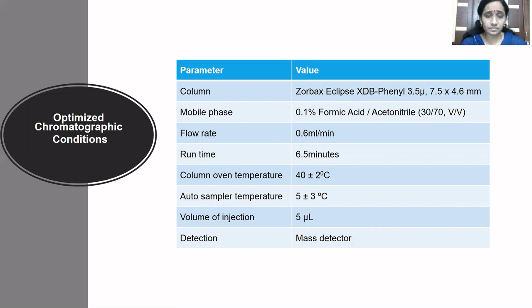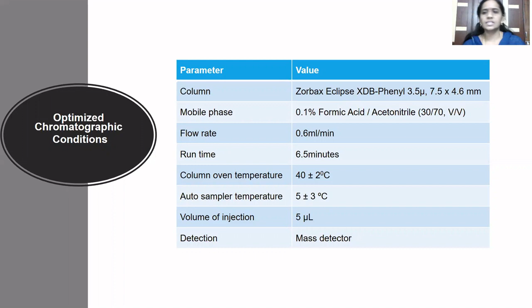Here, these are some parameters and their values mentioned in the paragraph is column. The Zorbax Eclipse XDB phenyl column is used, having 3.5 micron, 7.5 by 4.6 mm, and the mobile phase is formic acid and acetonitrile in the ratio of 30:70 volume by volume. The flow rate is 0.6 ml per minute, the runtime is 6.5 minutes, autosampler temperature is 5 plus or minus 3 degrees centigrade, column oven temperature is 40 plus or minus 2 degrees centigrade, injection volume is 5 microliters, and the detection is by mass detector.